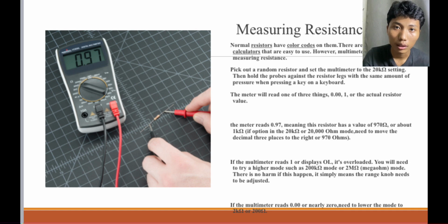If the multimeter reads 1 or displays OL, it's overload. You will need to try a higher mode such as 200k ohm mode or 2 mega ohm mode. There is no harm if this happens. It simply means the range knob needs to be adjusted. If the multimeter reads 0.00 or nearly 0, you need to lower the mode to 2k ohm or 200 ohm.